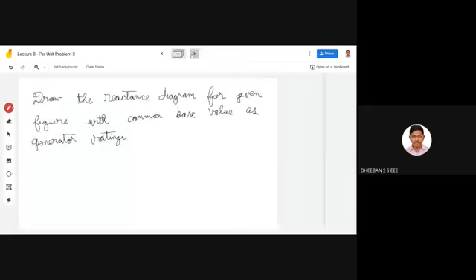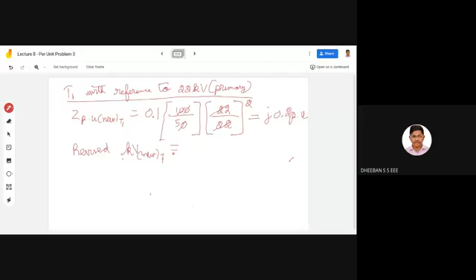So this is with respect to the primary. After finding the primary, you have to consider your revised value, since you are making a jump from primary to secondary. For revised kV, it is the given kV into your transformer ratio. So revised kV new for T1 will be equal to the given kV, 22, into your transformer ratio, 220 divided by 22, so you'll get around 220 kV.